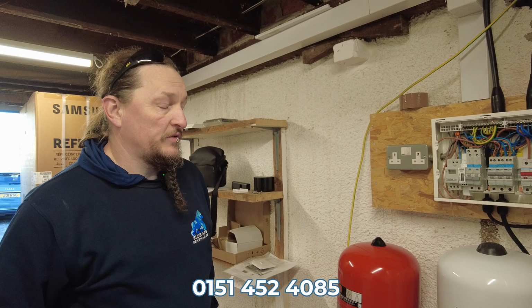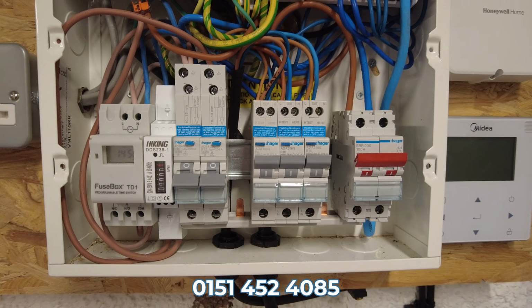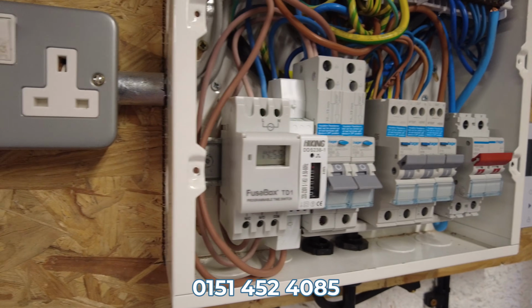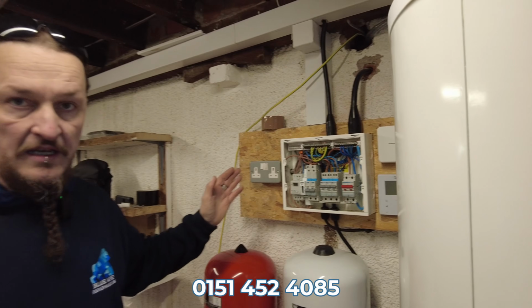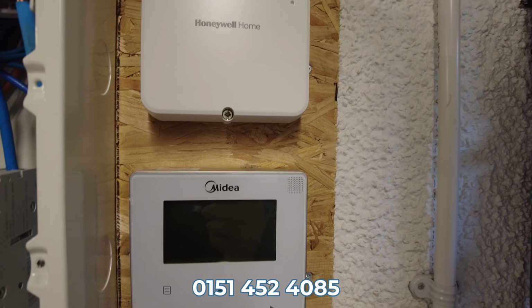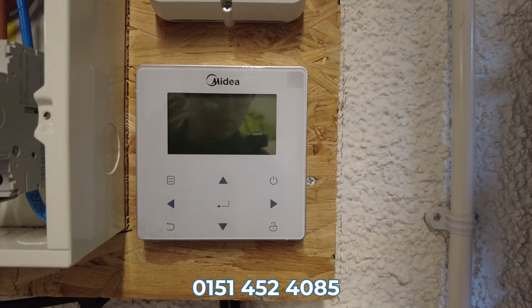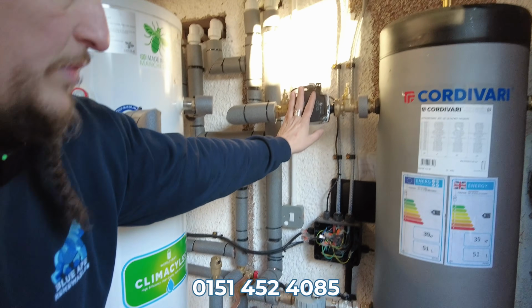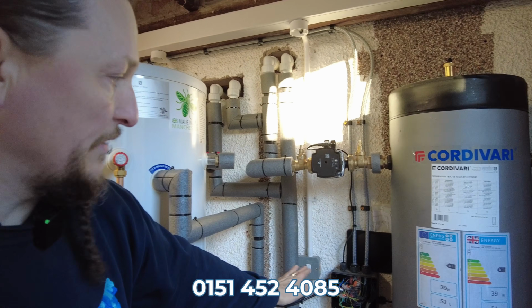So welcome to day 2 of the electrical, day 3 of the install, and I'll show you some of what we've done. We've got the distribution board that was already in the garage. We've got a separate circuit for the air source heat pump and for the immersion heater, an energy meter for the air source heat pump, and a timer for the Legionella cycle for the hot water tank. We've got the Midea controller, the thermostat receiver, and if we come over here, we've got the 270 litre hot water tank with a built-in thermostat, buffer tank, pump, 3-way valve, the wiring centre.